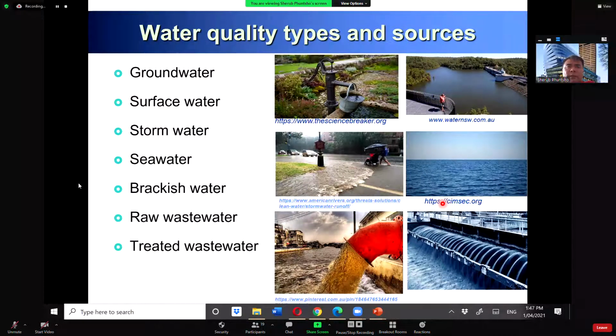All the wastewater coming from the toilets, the kitchens, the bathrooms, everyone in the Central Park building, is collected in the basement and treated to a very high quality, and then supplied back to the apartments and used for toilet flushing, for laundry, for irrigation of those green walls, and also for the cooling towers. In that way, they can significantly reduce the amount of fresh water required from Sydney Water.